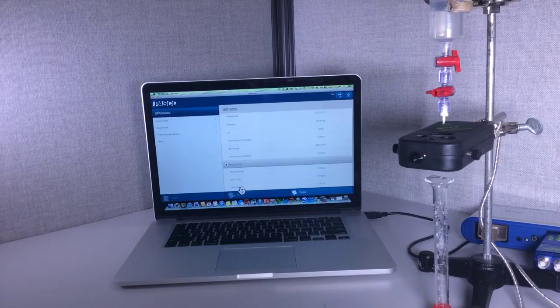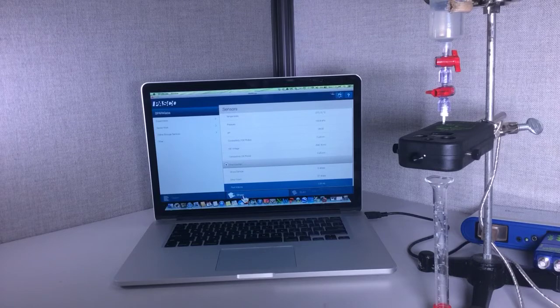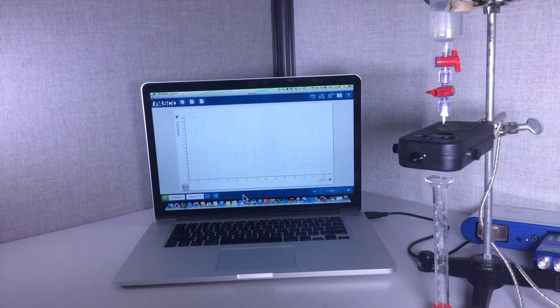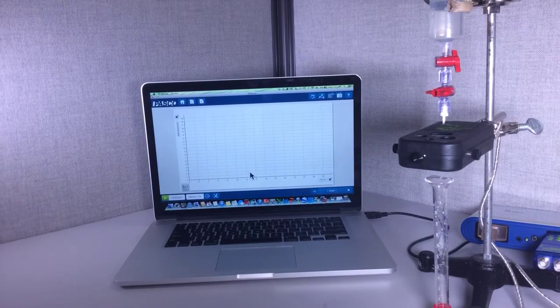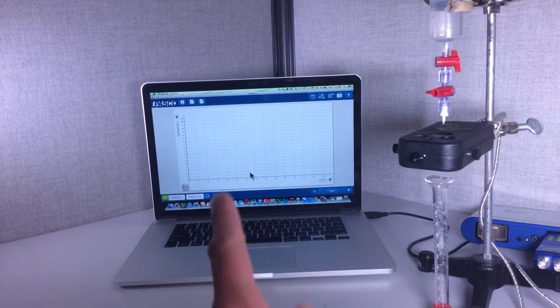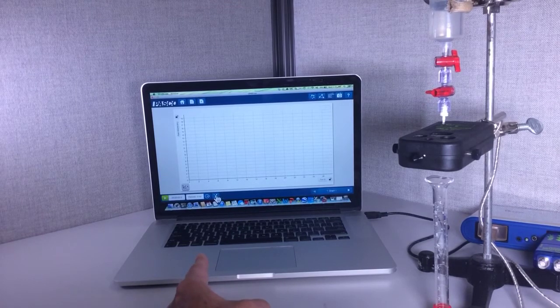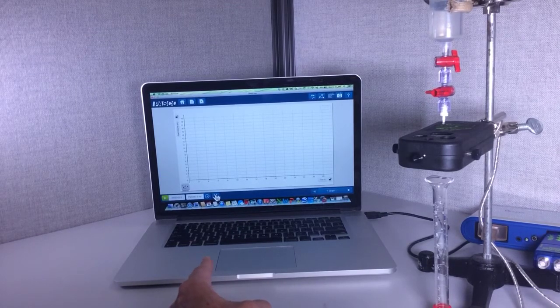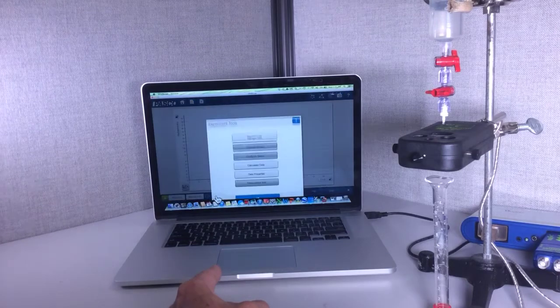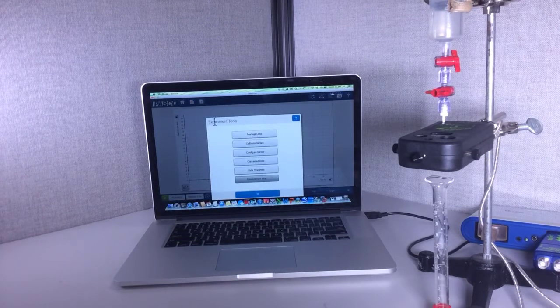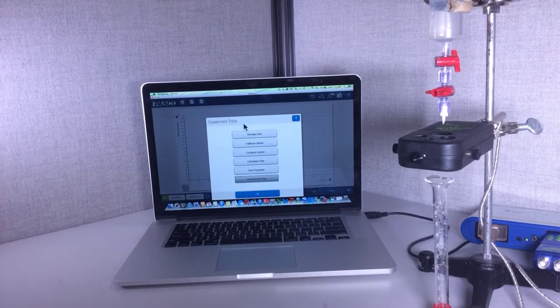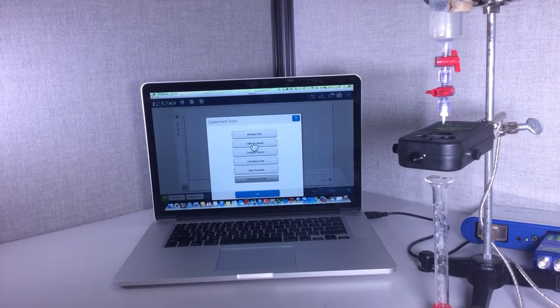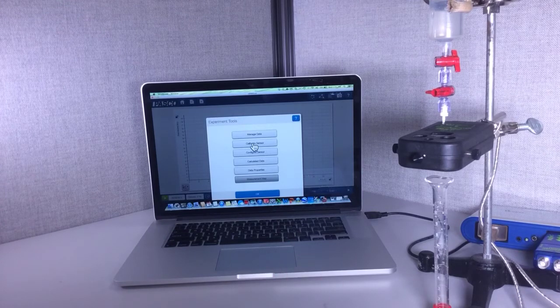I'm going to click on that and then hit show. If you notice, that's the only one available. This screen, this graph is irrelevant at this point. What I want to do is press the wrench and screwdriver. That brings up the experimental tools menu and second on that list is calibrate sensor.